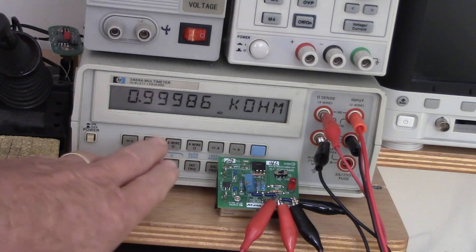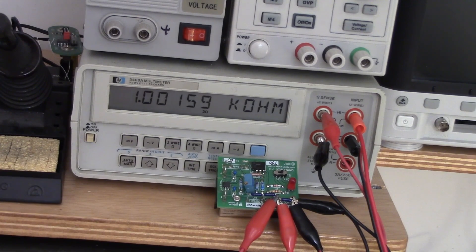I'll go back with 2-wire mode. The value goes up because of the extra resistance in those wires.